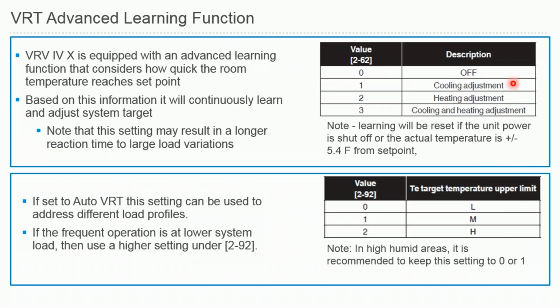So you can make this adjustment for cooling only or heating only, or you can do this for both cooling and heating as well. One thing you have to keep in mind, if there's a power shut off during the operation, the learning function will reset itself, and it will start analyzing the cycles, to see how fast the VRT can get to load requirements by changing the target refrigerant temperatures.